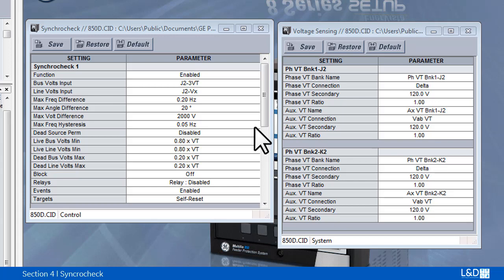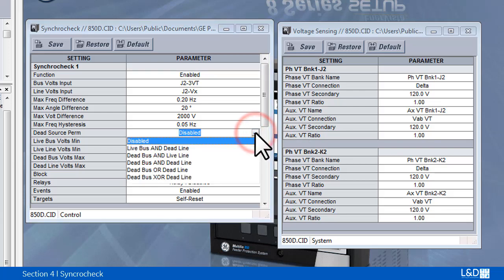The synchro check programming can allow permitted closure if either or both of the sources are de-energized. Dead source permission provides the combination of dead and live sources that bypass the synchronism check and permits the breaker to be closed when one or both of the two voltages are below the maximum voltage threshold. There are six options.